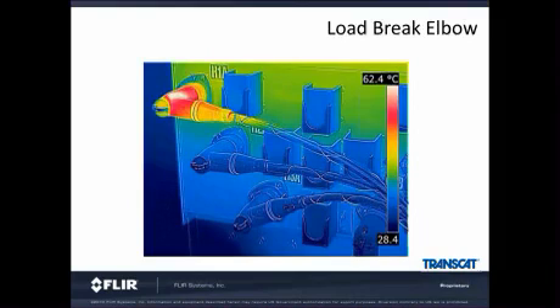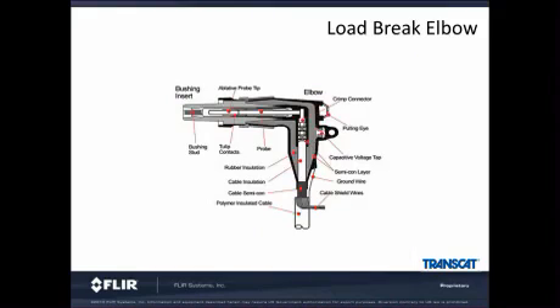The infrared camera can only see and measure the surface temperature of a target. We've discussed this in other applications such as the circuit breakers and transformers. However, the same is true when we have other indirect measurements, as we do in this case in the load break elbow getting warm. That's the one obviously in the upper left. The rubber boot acts like an insulator protecting the components inside. However, when one of these components gets hot, it takes a lot of energy to show up on the surface, as the rubber boot is thick.